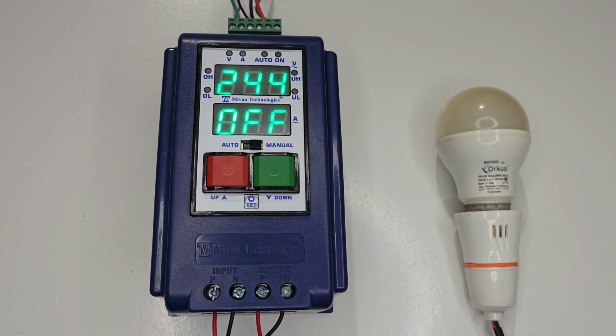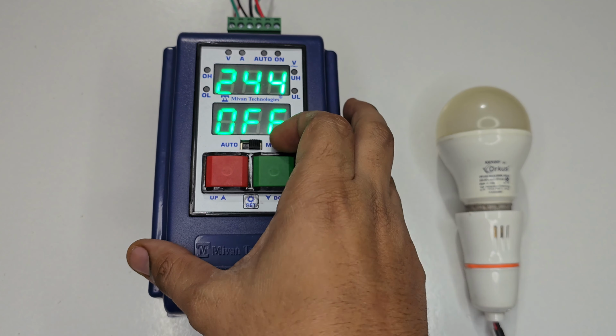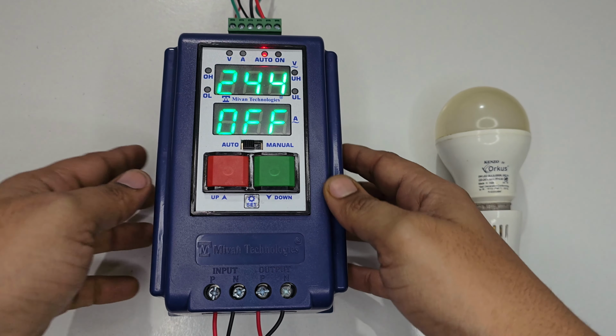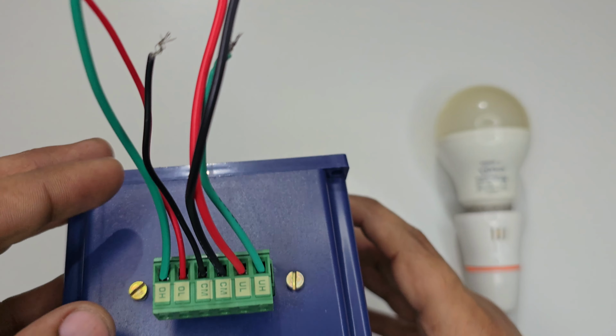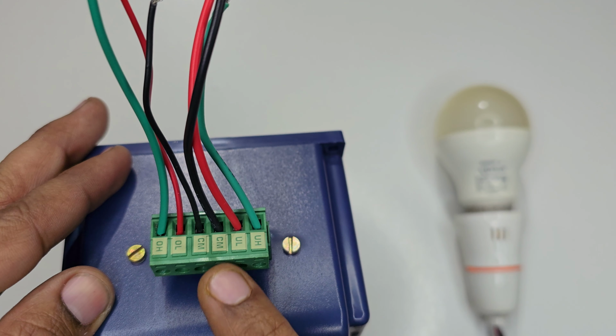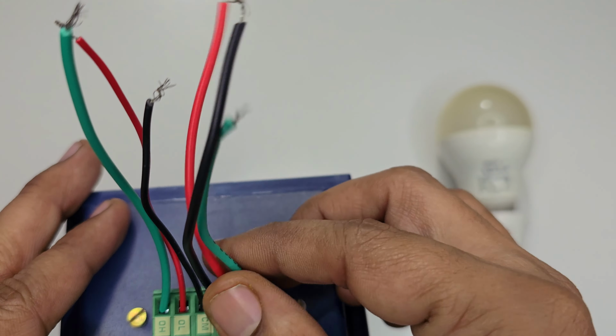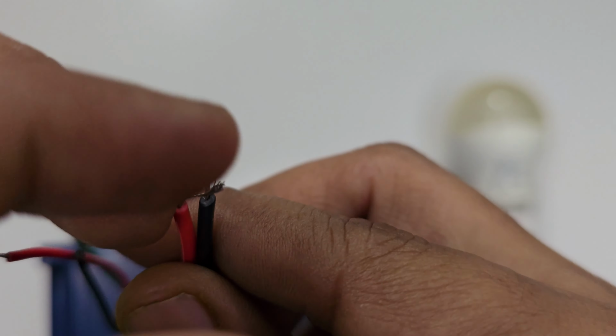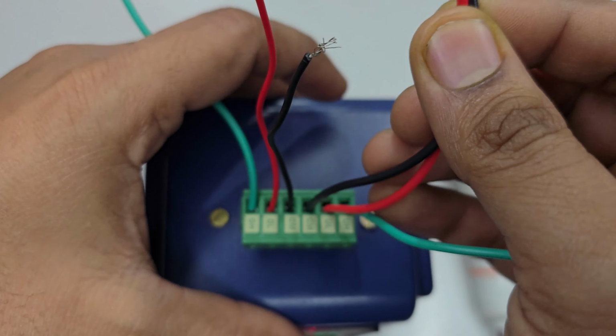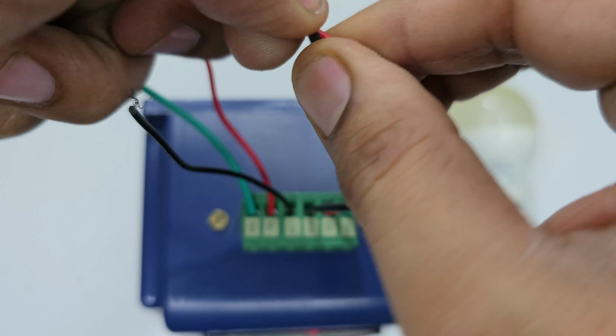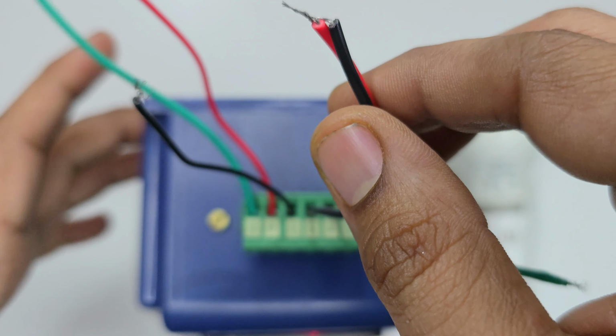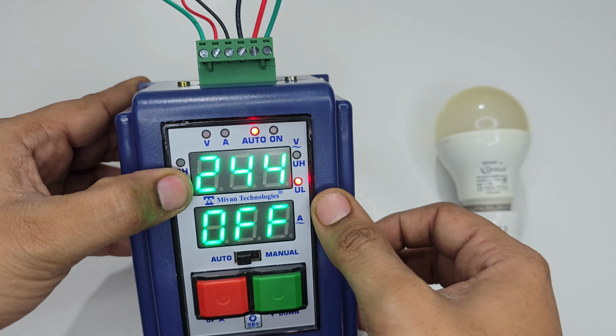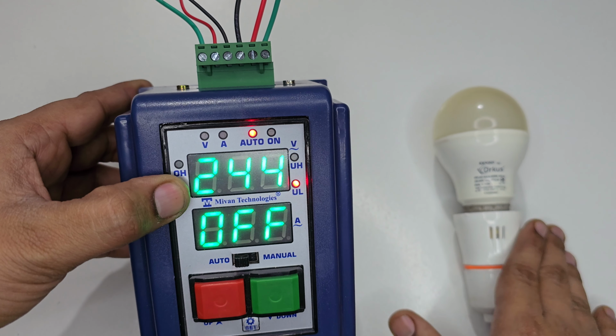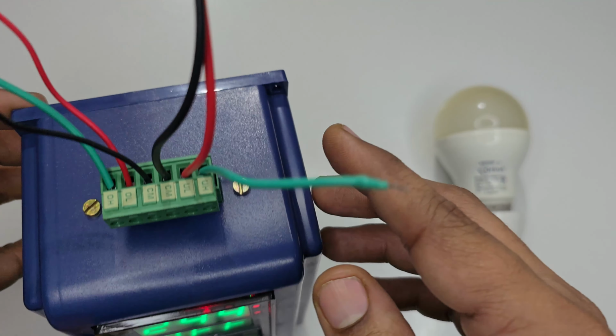Now let's test the device in auto mode. To test the device in auto mode, first put the device in auto mode. First short the common sensor to the UL sensor. When you short it, you can see the UL indication and the bulb remains in an off condition.